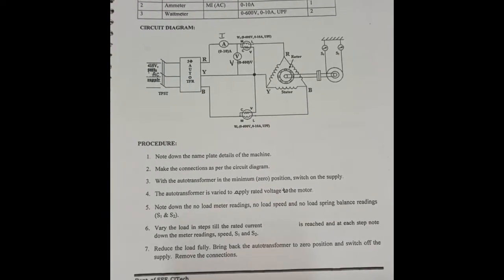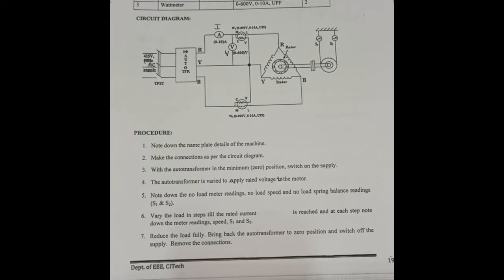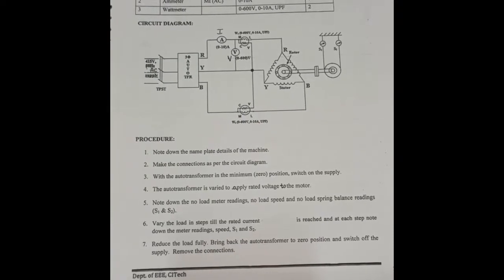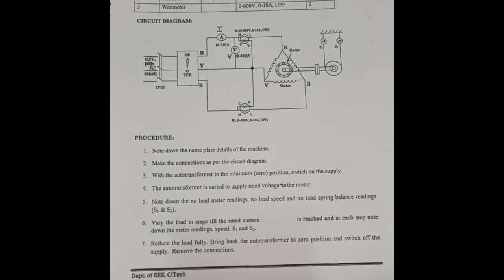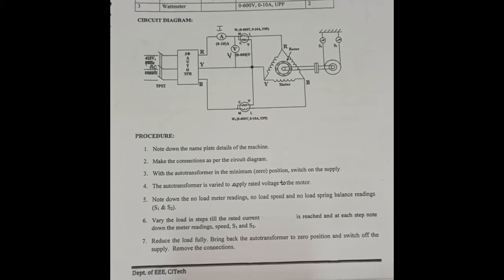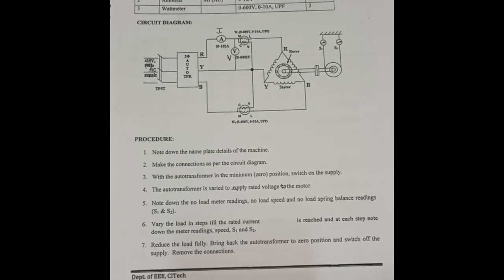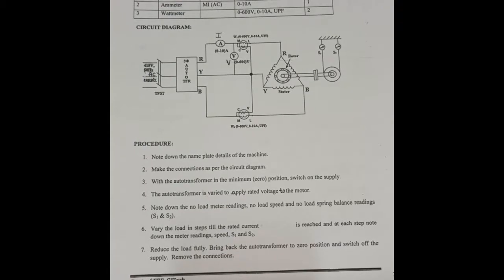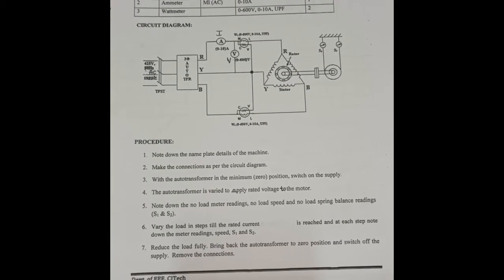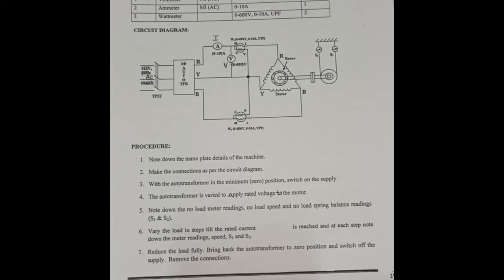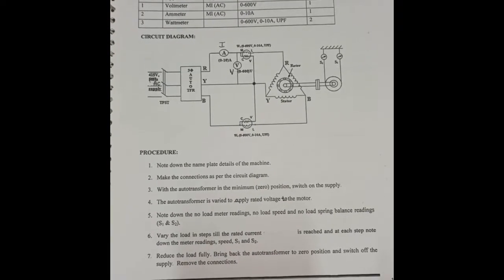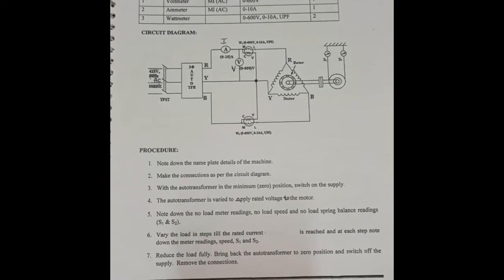Now, if any motor has to be chosen for a specific application, we first have to check whether the characteristics of the given motor are compatible with those of the application, and only then can we say this motor is apt for the given application. So load test is a primary test which is conducted on any given three-phase induction motor in order to study how this motor behaves when connected to the load.